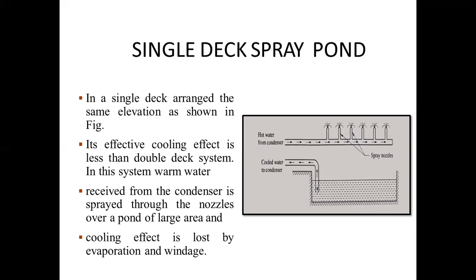Single deck spray pond, in this case there is a cooling pond. This is a cooling pond, and we are using a pipe in which we are using some nozzles. So this hot water comes out of the nozzles, and all the nozzles are at the same height in a single deck, arranged in the same elevation as shown. Its cooling effect is less than double deck system. In this system, warm water received from condenser is sprayed through the nozzles over a pond of large area, and cooling effect is achieved by evaporation and windage.